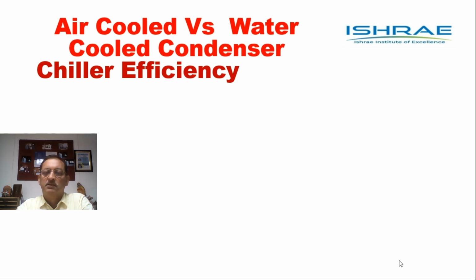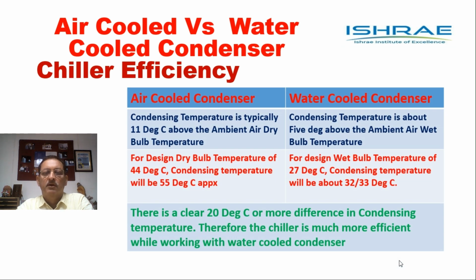Let's continue with this discussion, and first of all, we will talk about chiller efficiency, in an air cooled condenser and in a system where water cooled condenser is being used. The condensing temperature in an air cooled condenser is typically about 11 degrees centigrade above the ambient dry bulb temperature. Please note, I am talking about ambient dry bulb temperature, which is pretty high. In case we talk about Delhi, then the ambient dry bulb temperature for design is 44 degrees centigrade.